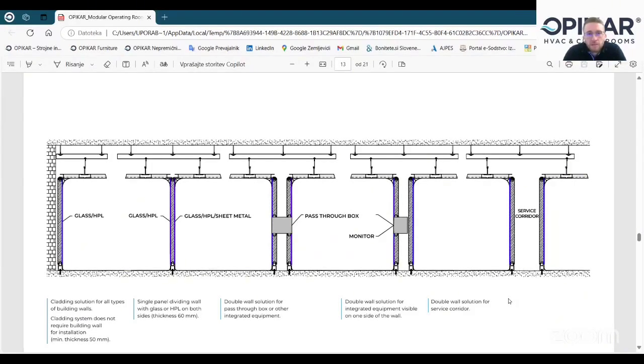We can basically make it from 5 centimeters to 1 meter. It can be as big as a person going inside, so the panels are not demolished from the operating theater side. The walls are always intact, always in their location, and from the other side, from the outside, there are doors to enter this technical area. There can be different dimensions in between to put in monitors or pass-through boxes or installations, etc. And the last one is, like I said, the service corridor, technical area. So cladding and partition wall.